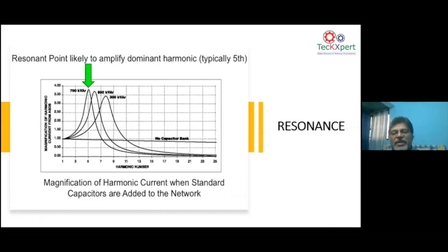In both situations, the end effect is the same. Voltage goes up, current goes up, and accidents of fire happen. Now, as you keep adding more and more capacitors into the network, I showed you a little before, when you have 400 kVAr, your natural frequency is somewhere around 322. As you keep putting in more and more capacitor bank, the resonance point, the natural frequency, keeps coming down. If you put a 700 kVAr capacitor, then you have a natural frequency very close to the fifth harmonic. It is at the fifth harmonic itself. That means you will have a parallel resonance. So whenever you put capacitors in parallel with a transformer, you should always make sure there is no problem with regard to parallel resonance.